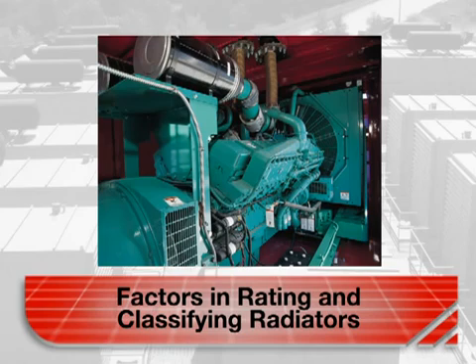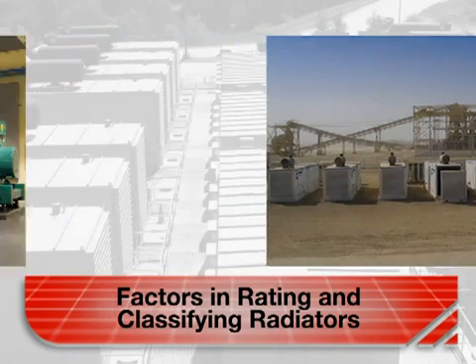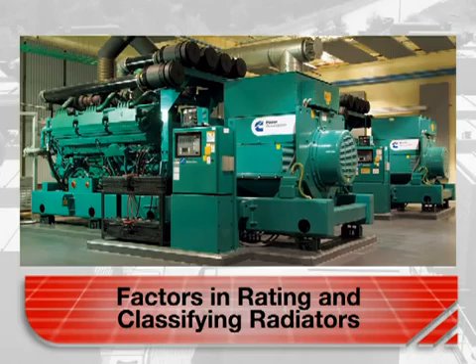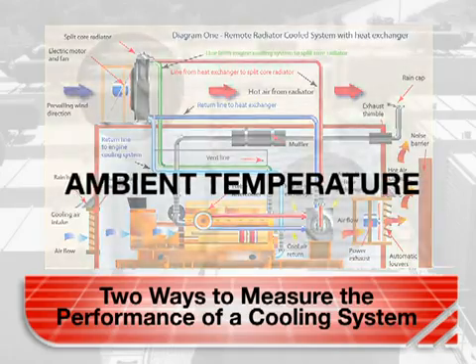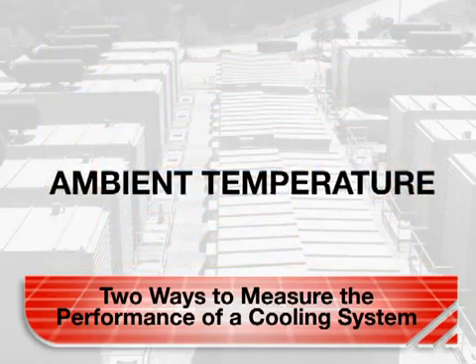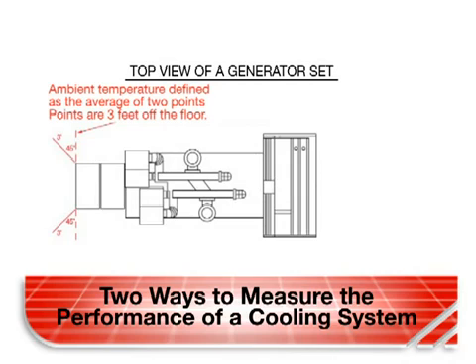Now we dive into the details of rating and classifying radiators. These are the factors involved: where they are installed, the temperatures they are rated to handle, and how those ratings are determined. There are two ways to measure the performance of a cooling system: ambient temperature and what's called the air on core, or AOC. When a cooling system is rated for ambient temperatures, what is measured is the temperature of air on the inlet side of the system, before it picks up heat from the alternator and the engine components.